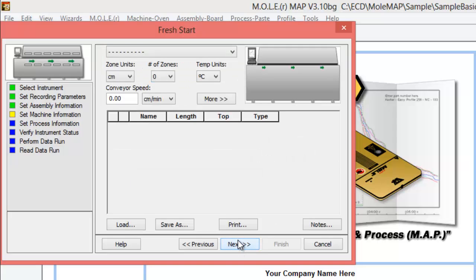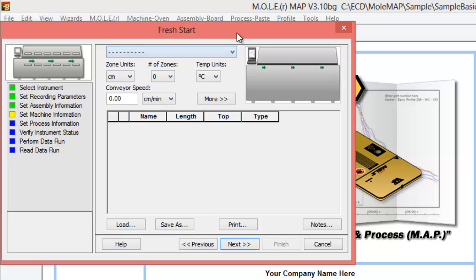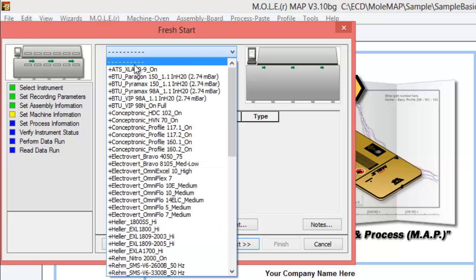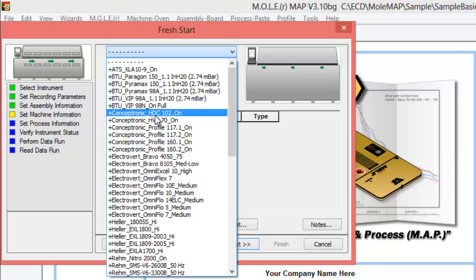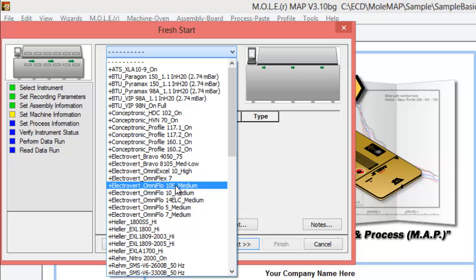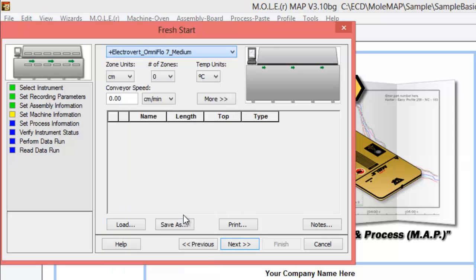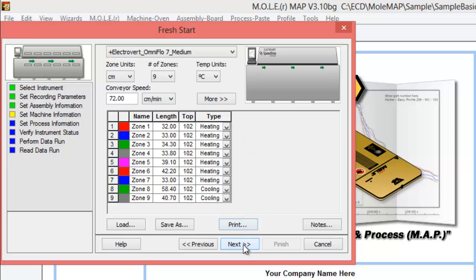Now it's going to ask you for your oven information, your machine info. You can either select one from the list or if you've already created one under the machine oven drop-down menu, that would be located at the top of the list here for a custom created oven that you've measured the zones on. I'm just going to say we'll go with our OmniFlo 7 oven here with seven heating zones and two cooling. You can make any modifications here if you need, and we'll go ahead and click next.